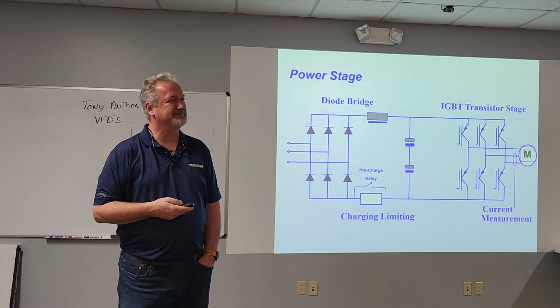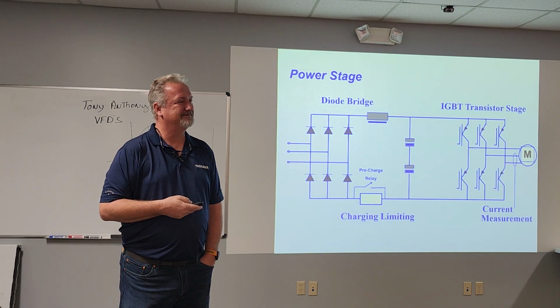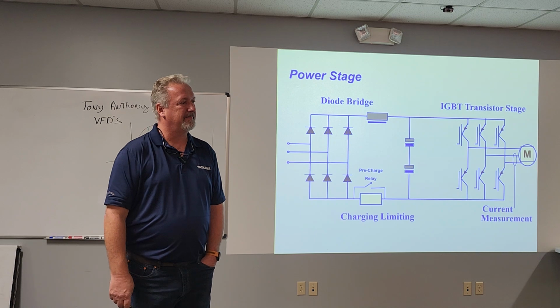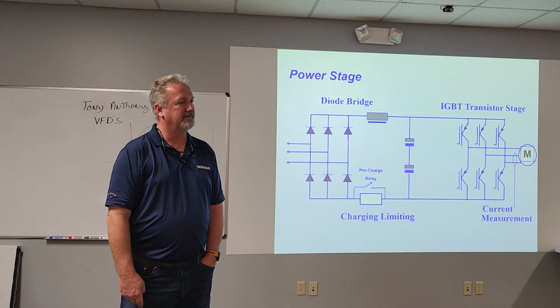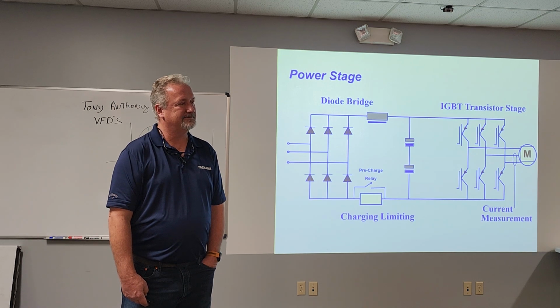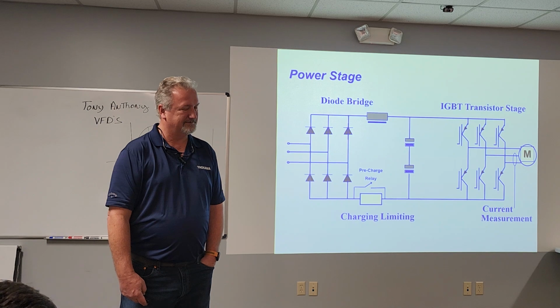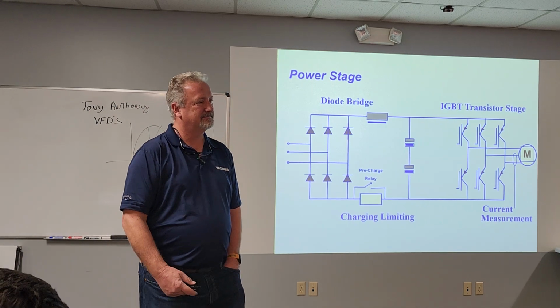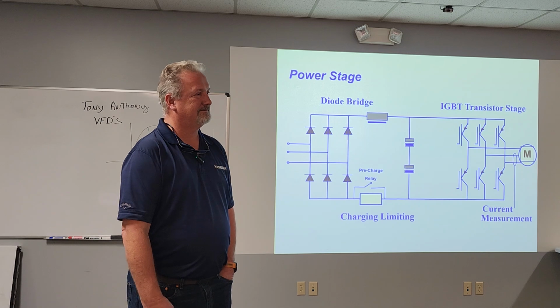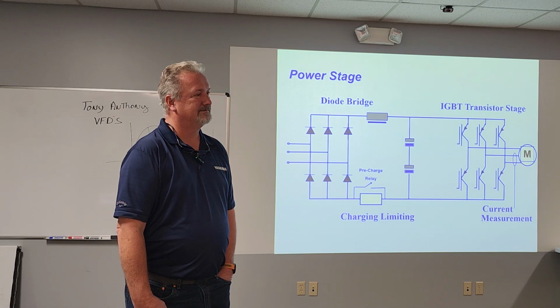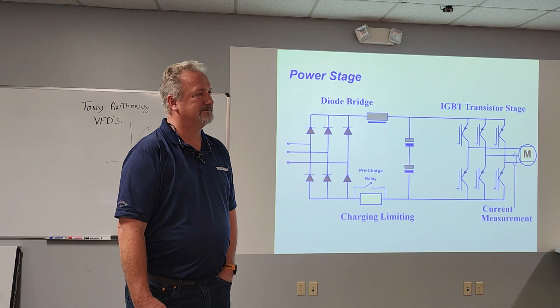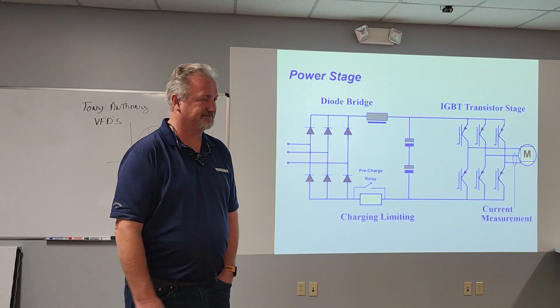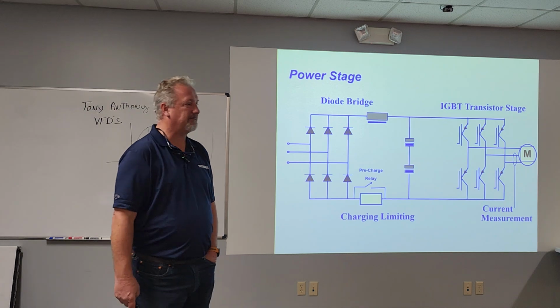And the definition, I have said over and over again, what is the definition of single phase? Less than 3 hots. 1 hot, single phase. 2 hots, single phase. 3 phase, 3 hots. If it ain't, it's single phase. If this building has 3 phase, and I call the electric company and say the building is single phasing, they know that less than 3 hots are working. You've lost 1 leg.